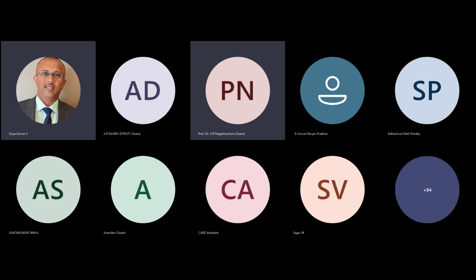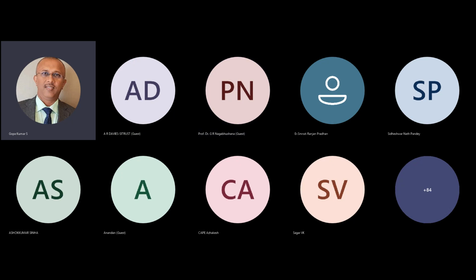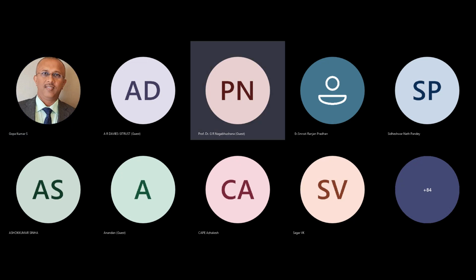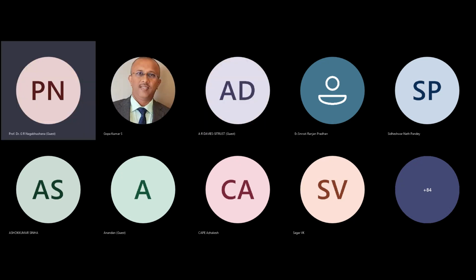Sir, one interesting question: is any sharp tip required for an air termination rod? A very good question. In fact, a very, very good question. Many people think the sharper the tip, the better it is. It's not really true. The reason is that a very sharp tip has a very high electric field intensity under the approaching leader. The very high field causes local ionization surrounding it. When local ionization is there, it has both positive and negative charges.